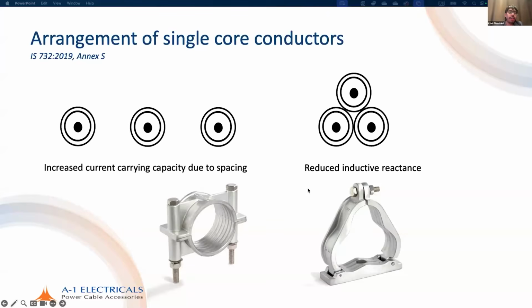Now, you'll see that there are two types of cleats that are very common. One is for a single cable and one is for three cables. Single cable cleats are either used for multi-core cables or for three single core cables in a flat formation, or four as it may be. This allows for an increased current carrying capacity because there is no effect of grouping. However, there is a relatively high and imbalanced mutual inductance because these are not symmetrical.